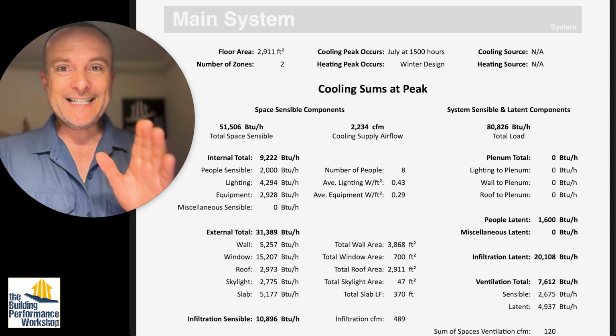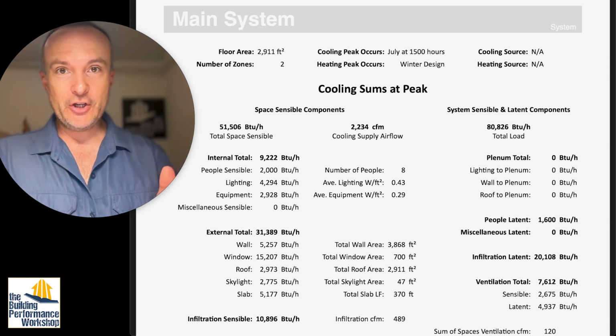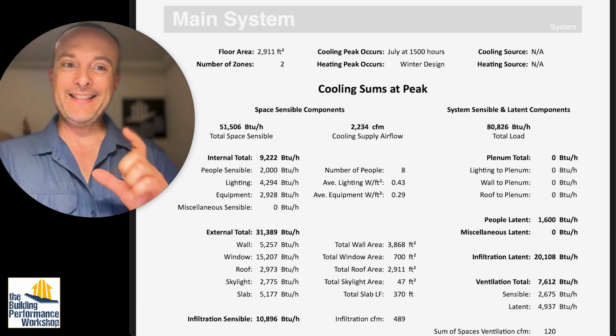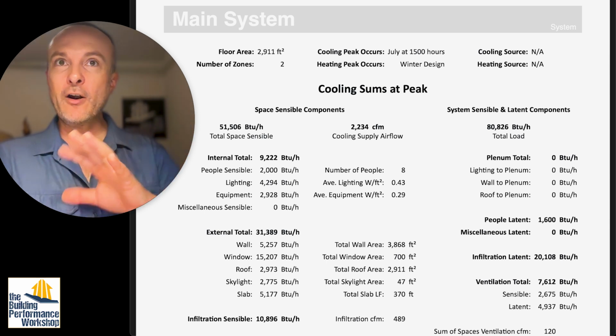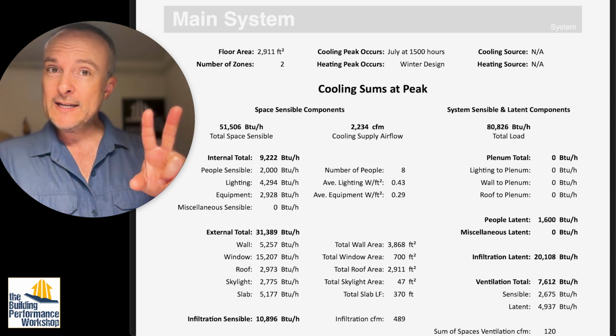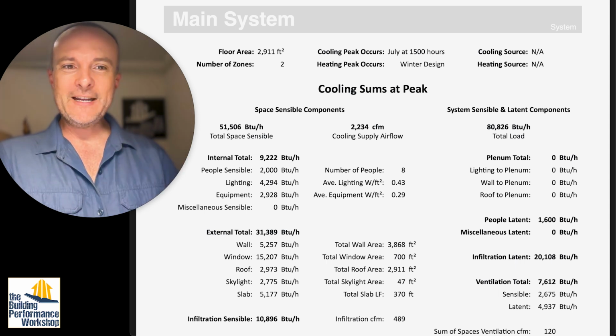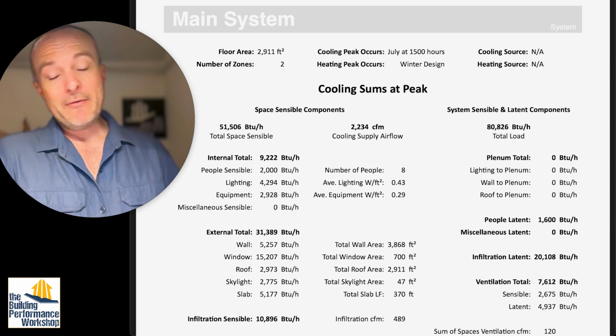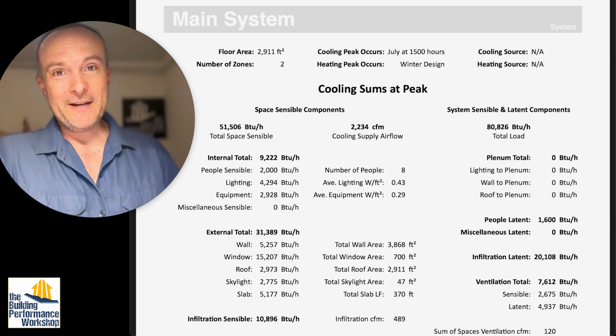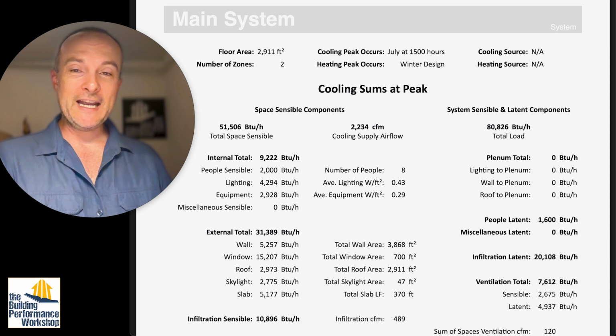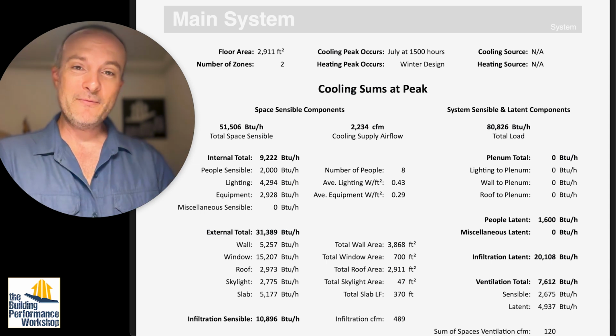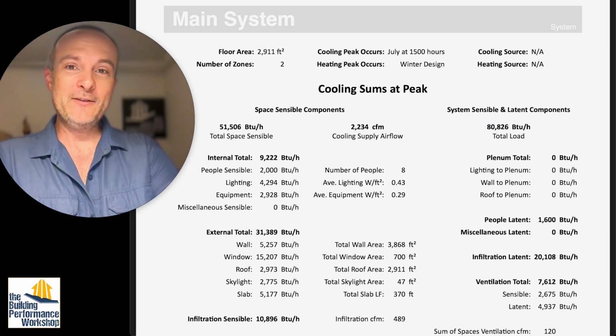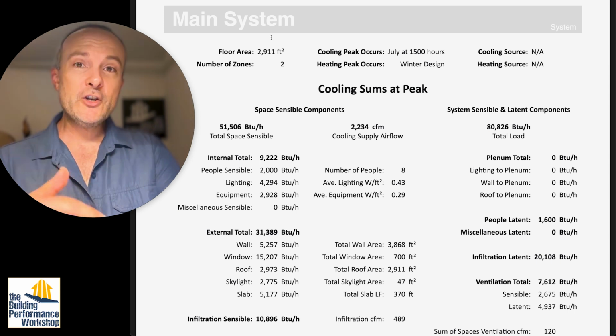First of all, if it doesn't say on it somewhere Manual J or ASHRAE approved heat load calc, then there are a bunch of different ways that are approved per code to calculate heating and cooling. Some of them are wrong, and we've talked about that, even with Manual J. Manual J has some fat built into it in some weird places, and they're rewriting it right now in response to that. But we want to just check some things.